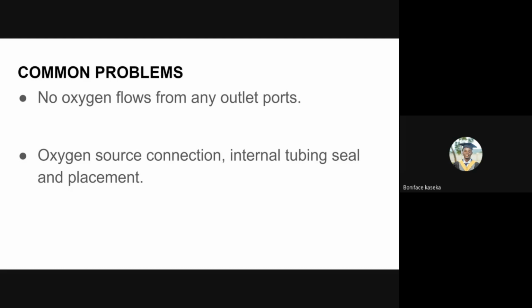As such, you cannot produce any oxygen. And sometimes it can also happen that in the internal tubing there's some displacement or some loose fitting, which means that oxygen is just escaping and it's not getting out into the outlet tube. So those are the possible causes for such a problem.